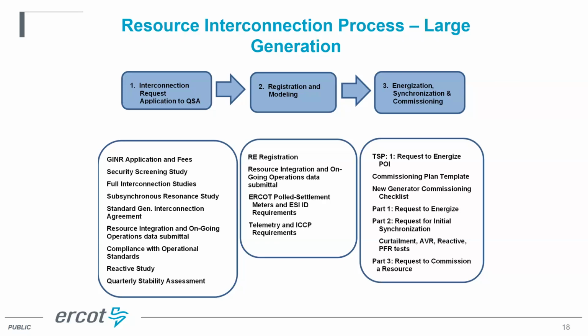The developer has to submit a plan on how they plan to commission the resource, then go through a new generator commissioning checklist, which has 3 parts. Part 1 is request to energize their facilities, so everything except the generator gets energized. This lets us check some of the telemetry and set transformers and so on.